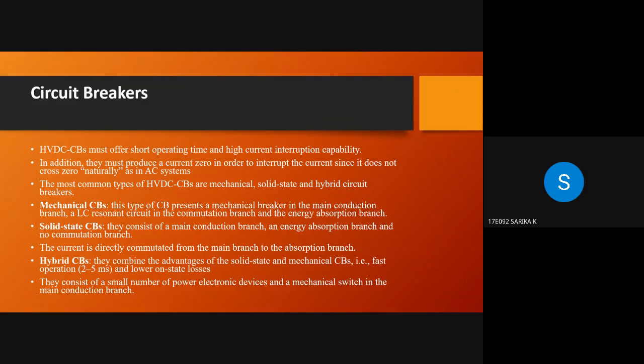Hybrid circuit breakers. They combine the advantages of the solid state and mechanical circuit breakers, that is, fast operation in the range 2 to 5 milliseconds and lower on-state losses. They consist of a small number of power electronic devices and a mechanical switch in the main conduction branch.